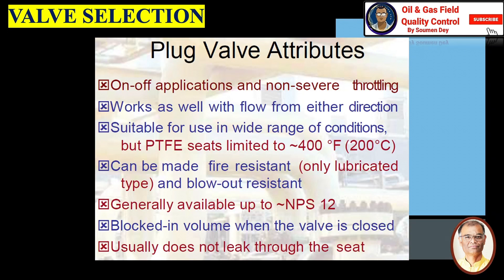Plug valve attributes: on and off application, non-severe throttling, works with flow from either direction, suitable for use in a wide range of conditions. PTFE seat is limited to 400°F (200°C). Can be made fire resistant — lubricated type only — and blowout resistant. Generally available up to NPS 12. Blocked-in volume when the valve is closed, and usually does not leak through the seat.